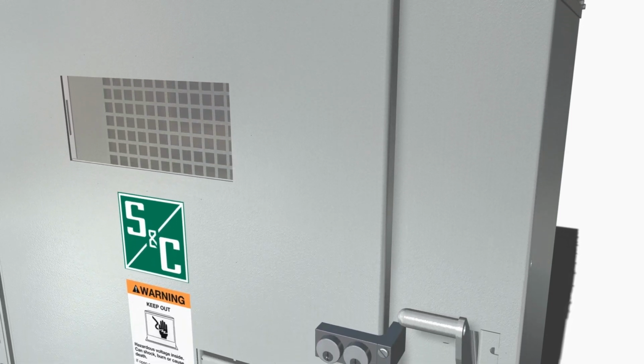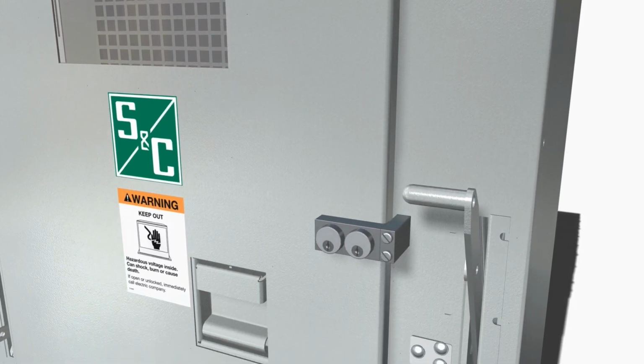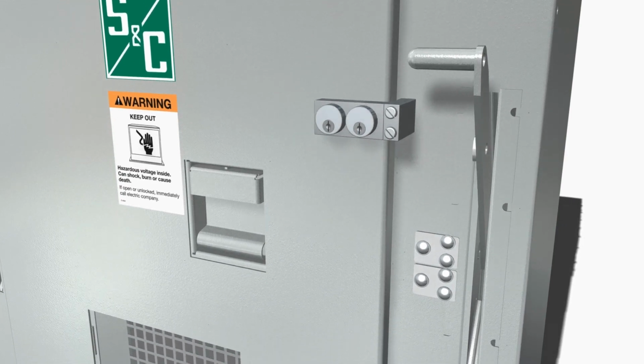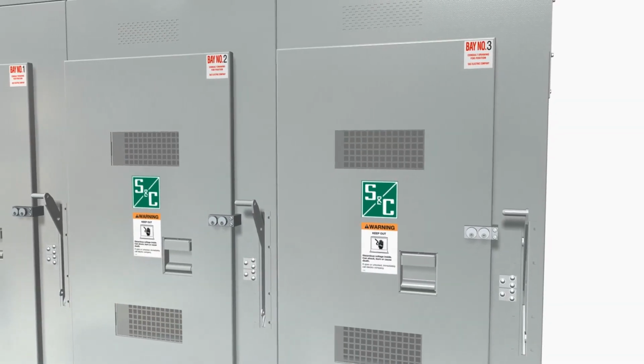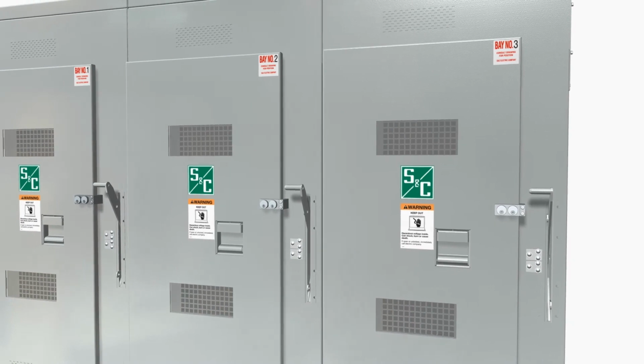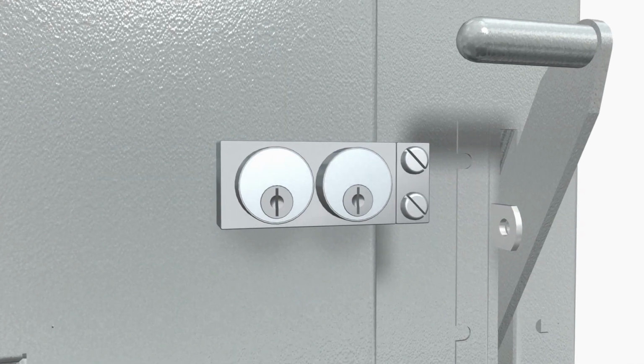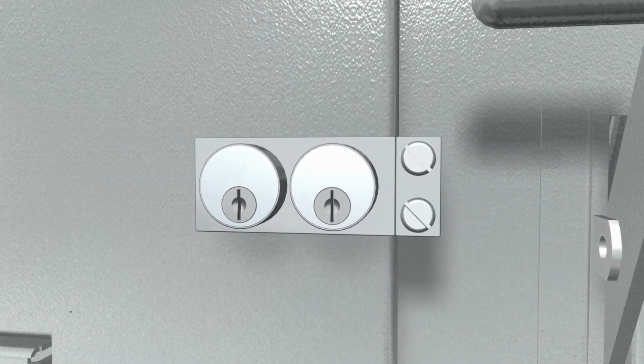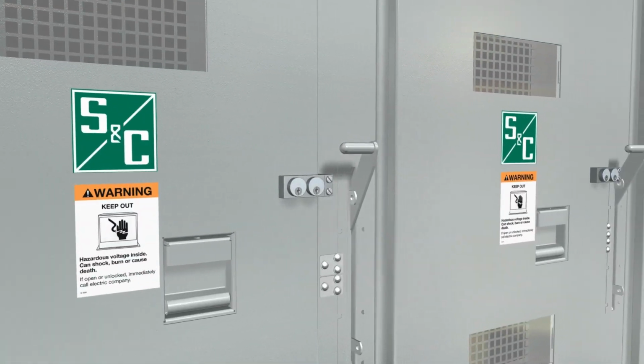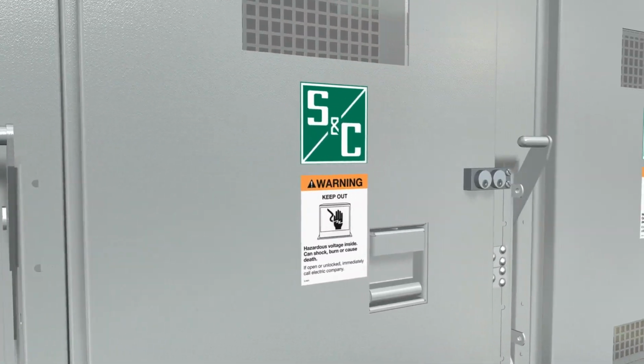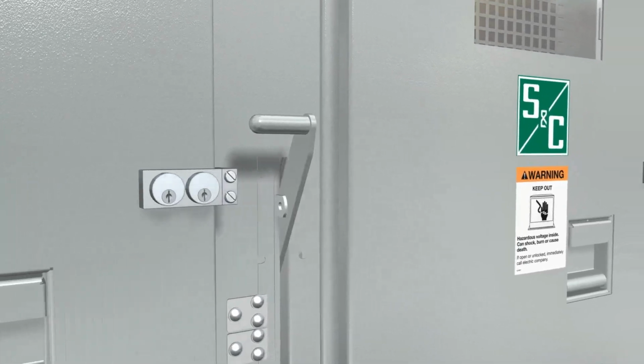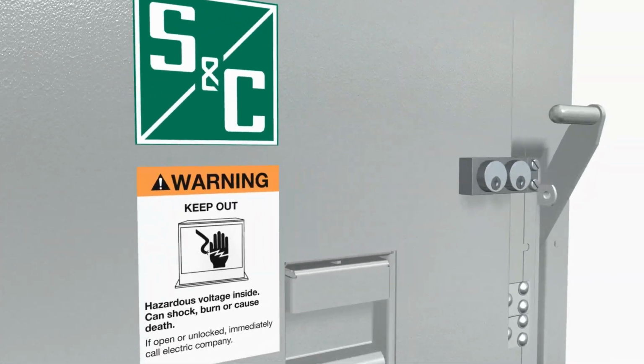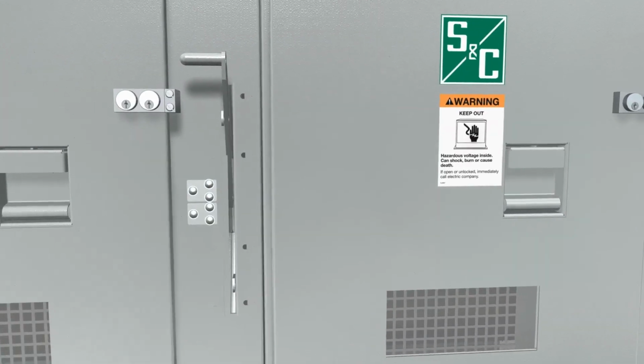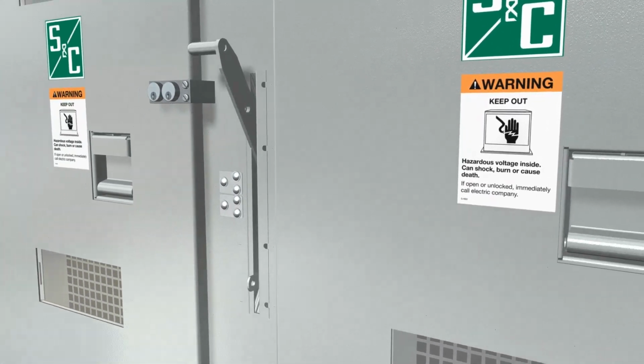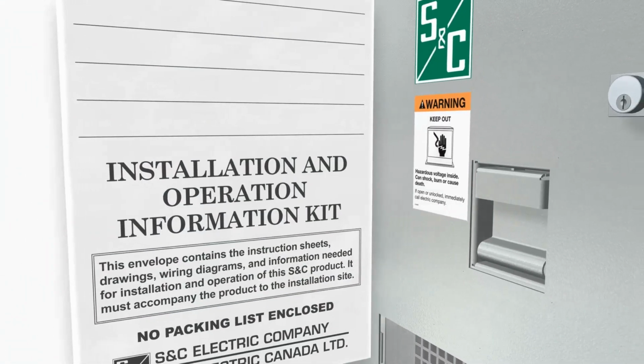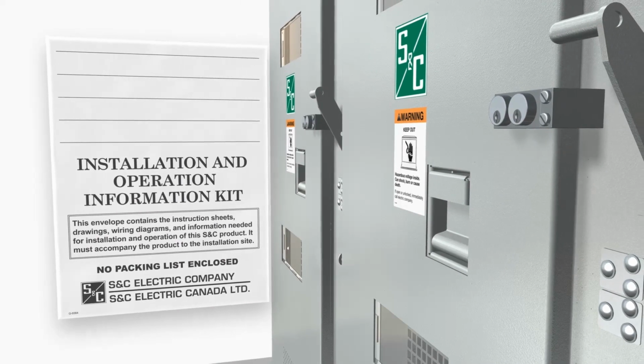Key interlocks mounted externally and where the key is retained in the operated position are sometimes shipped separately to prevent key breakage during shipment. Install such interlocks with the bolts provided. The key sequence of the system is indicated on the one-line diagram on the CDA-CDT drawing. Where complex key interlock schemes are furnished, refer to the applicable RD or CDT drawing.